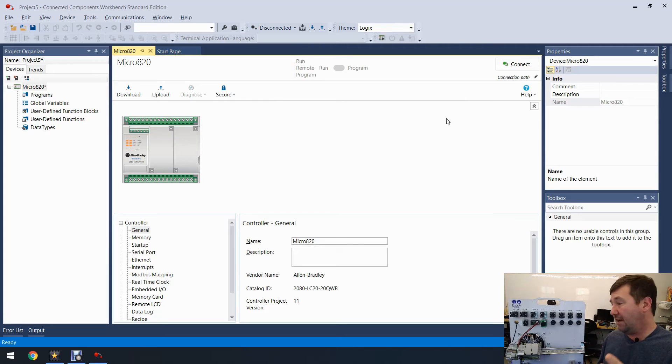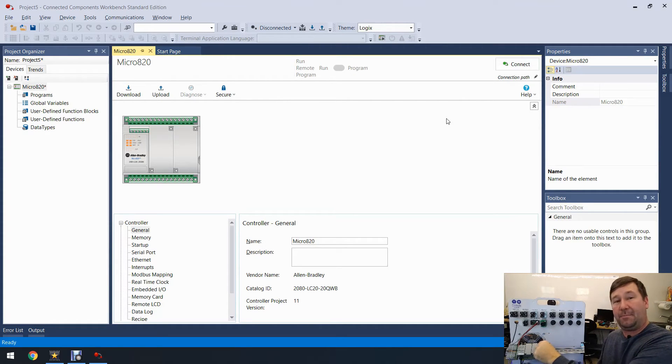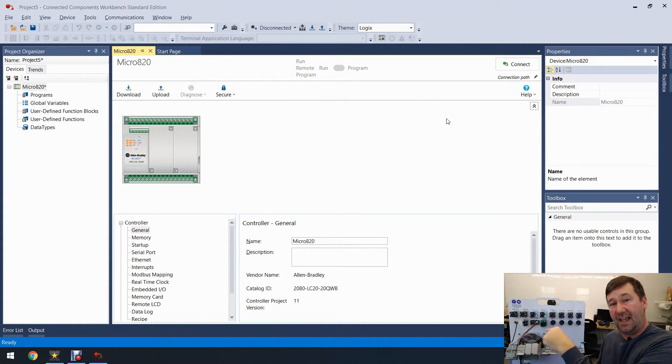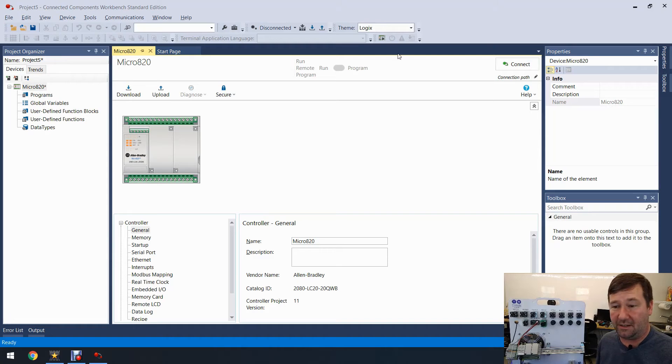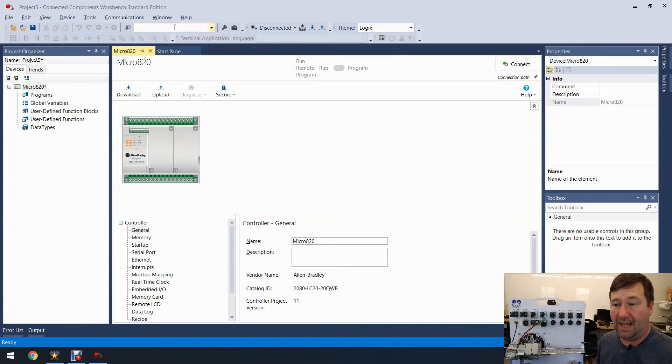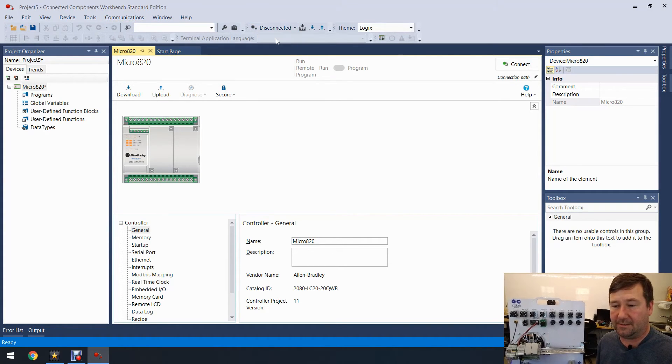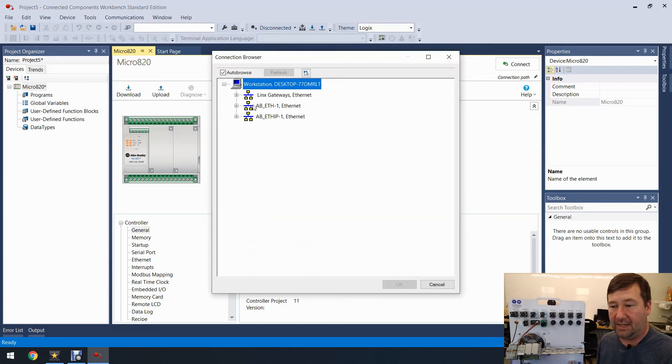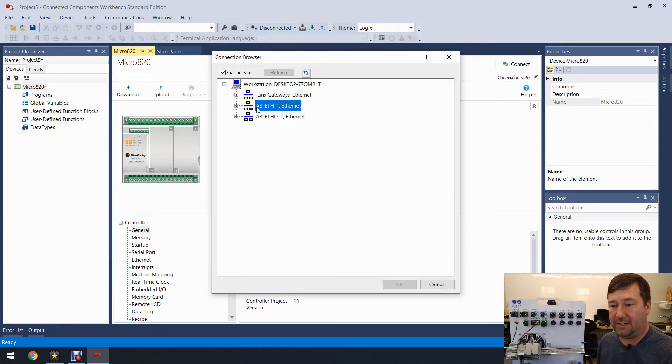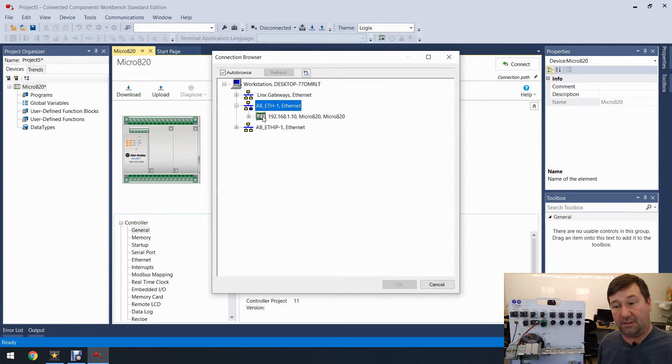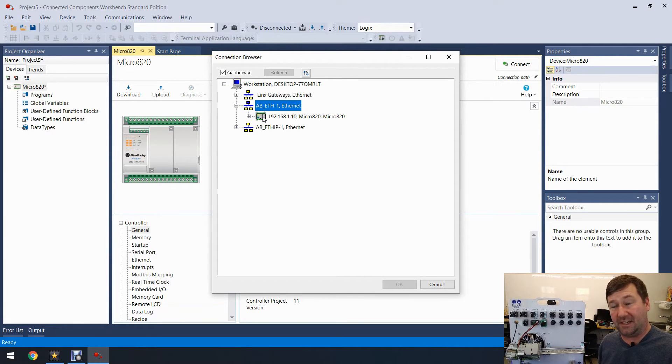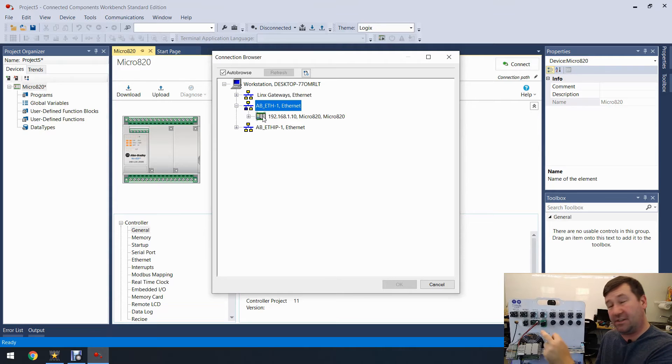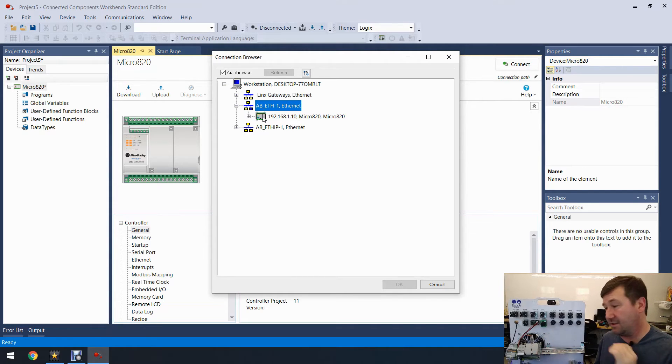What that's going to do is it's going to tell it, instead of, remember the Ethernet/IP driver it just listens? Well the Ethernet Devices driver now is going to go and look at that IP address and say 'Hey, is there a PLC right there?' So let's go back to Connect and the Ethernet driver. So now it can see the PLC also. So that's the two drivers that you can use to connect over ethernet to your PLC.